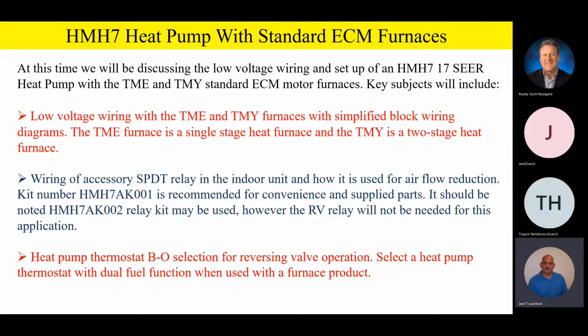Now, concerning furnaces, please remember the heat pump thermostat still has to have that BO selection for reversing valve operation. And please select a thermostat with dual fuel function if you're going to be using it with a furnace product. So let me stress that one more time. Make sure that whatever heat pump thermostat that you use has got a dual fuel function, because the dual fuel function will be driven from the thermostat levels.